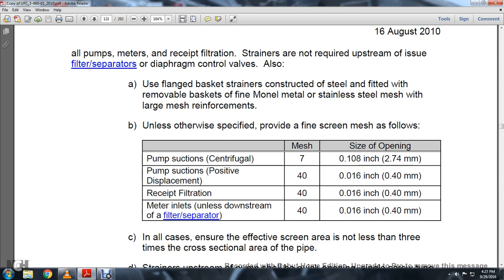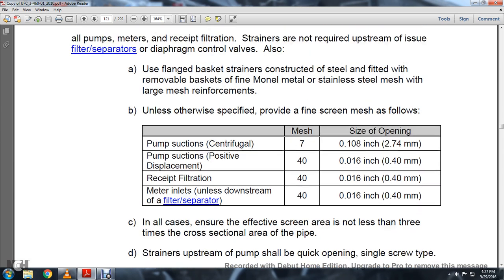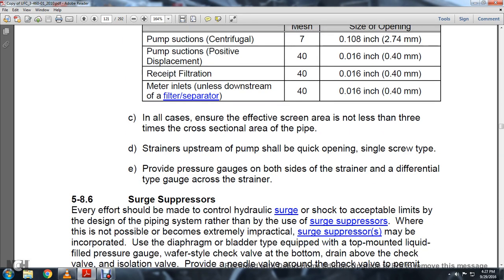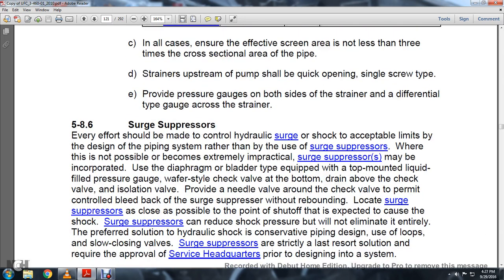Positive suction positive displacement: 40 mesh, 0.016 inch. Receipt Filtration: 40 mesh, 0.016 inch. Meter installation unless downstream filter: 64 mesh, 40, 0.016 inch. In all cases, ensure the effective screening area is not less than three times the cross-sectional area of the pipe. Strainers upstream of pumps shall be quick-open single-screw type with pressure gauges on both sides, or a differential-type gauge, to indicate the condition of the strainer.